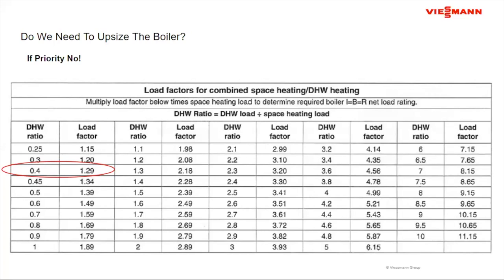This one happens to be a chart that I got from a friend. The other way that I also do it is out of the ASHRAE manual. They have a chart, and the chart number in the ASHRAE manual is applied to the domestic hot water. But this allows me to go in here, and based on the domestic hot water load and the space heating load, calculate a load ratio. And based on that ratio, it'll tell me that there's a load factor. So for instance, if my ratio is 0.4, my load factor is 1.29. And I multiply my load by that 1.29 to cover the application.